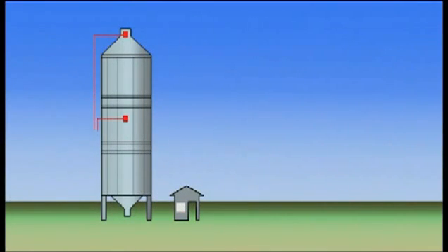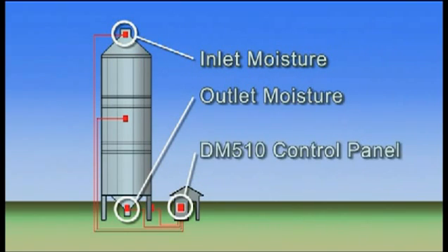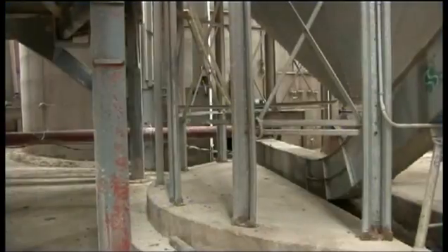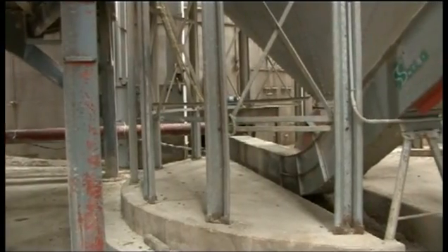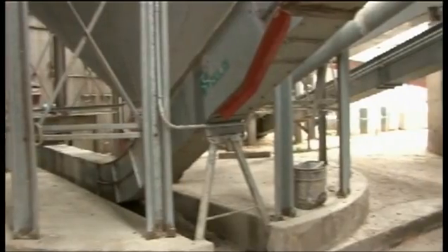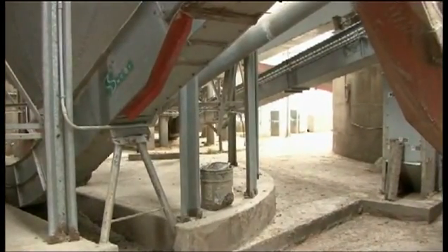The Dryer Master uses online moisture and temperature sensors located at the inlet and the outlet of the dryer, as well as the drying air temperature. Several times a second, these sensors provide moisture and temperature readings to a computer located in the Dryer Master control panel. The computer uses this information to build a model of how your dryer is operating. Then, as inlet moistures and drying conditions change throughout the day, the Dryer Master continuously calculates and automatically adjusts to the best discharge rate for the current situation.